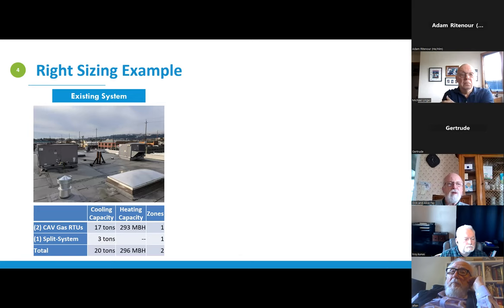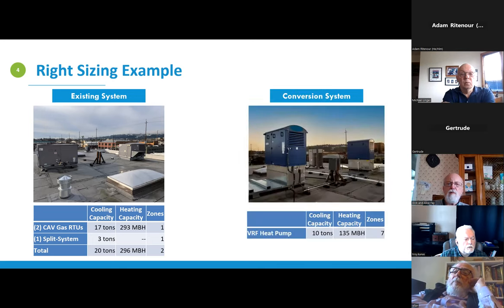And the final key component of VHE DOAS is right sizing that heating and cooling equipment. So this example comes from the Energy 350 office, which is in Portland, Oregon. In 2020, we actually converted our RTU system to a VHE DOAS system. And what we did was we had two constant air volume gas RTUs. And we converted that to a VRF heat pump system. And then we also added those two HRVs to the rooftop to make it a VHE DOAS system.